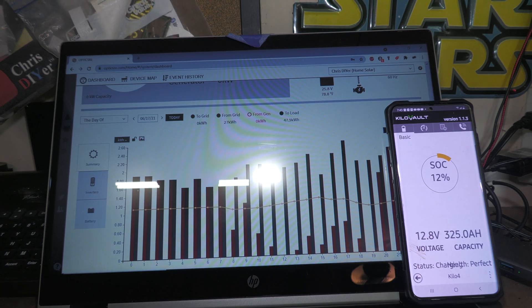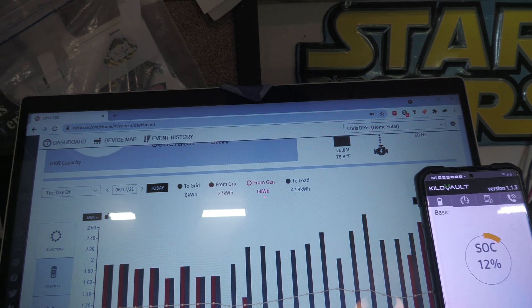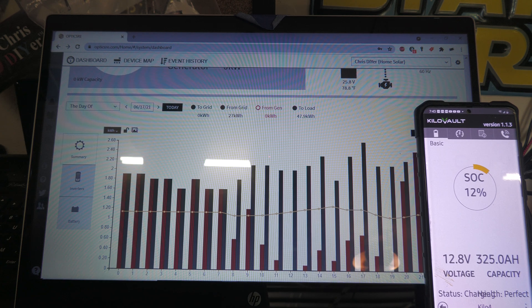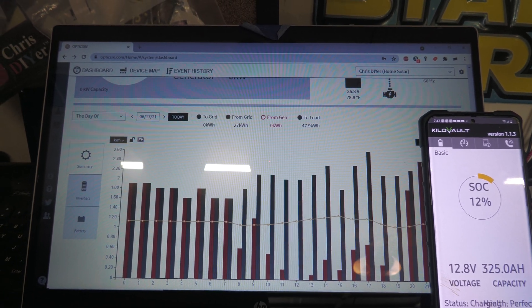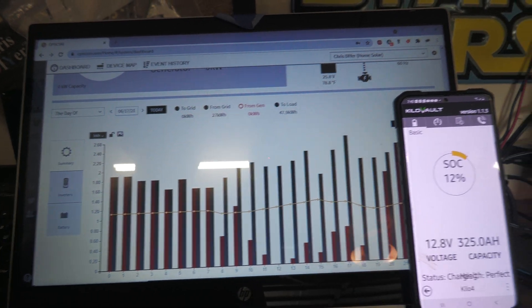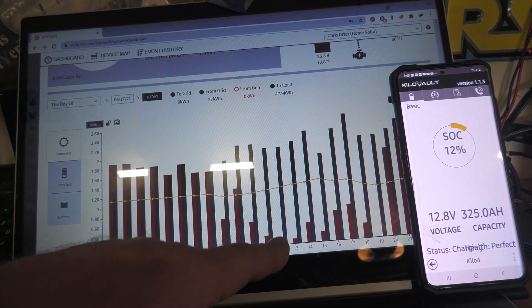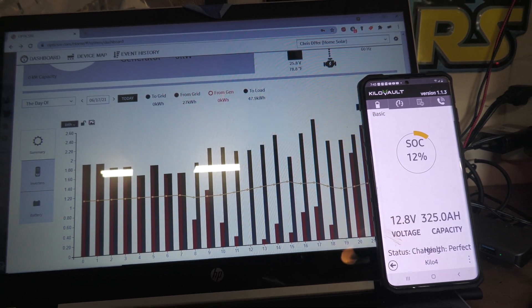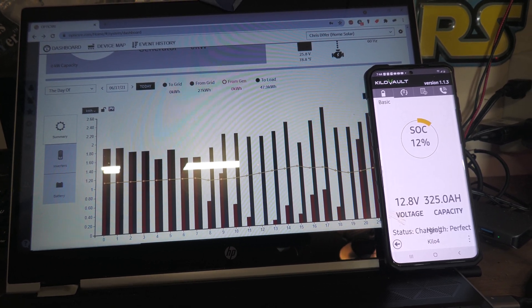Let me turn the light off here. So yesterday — this is a graph from yesterday — my loads were about 48 kilowatt hours but I only used 27 from the grid, so about a 20 kilowatt hour offset. But you can see right down here, even though I had good battery voltage, the inverter would just kick on and use grid power. It shouldn't be doing that because my loads aren't above what the inverter is capable of doing.